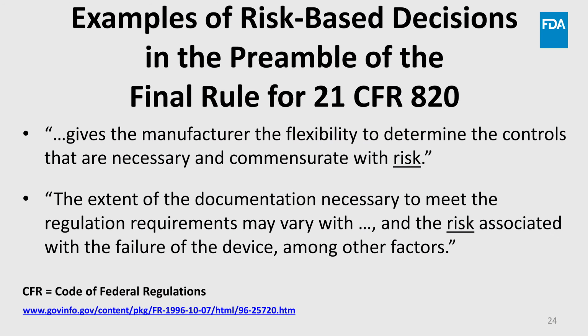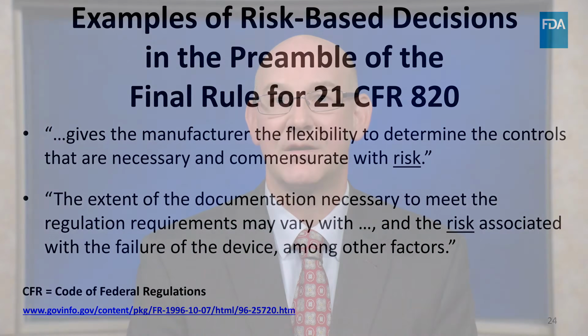And concerning the amount of documentation needed for your quality system, the extent of the documentation necessary to meet the regulation requirements may vary with the complexity of the design and manufacturing operations, the size of the firm, the importance of a process, and the risk associated with the failure of the device, among other factors.